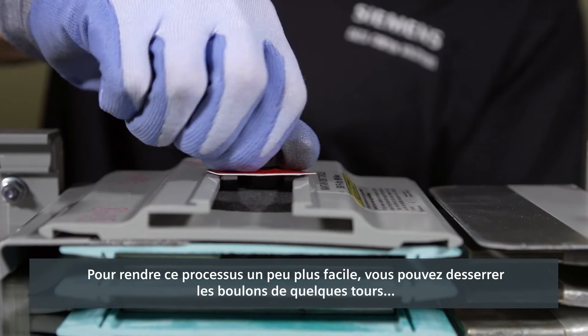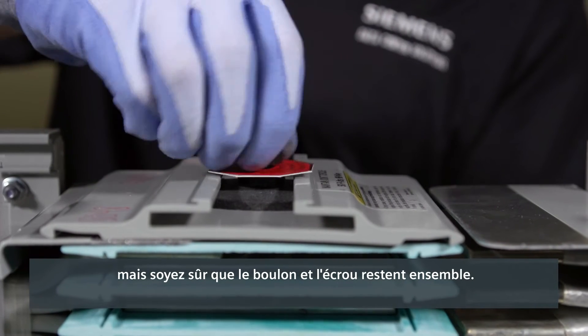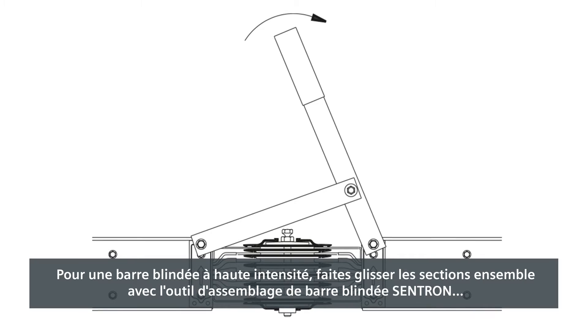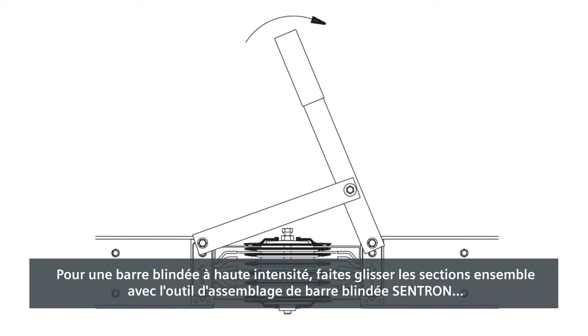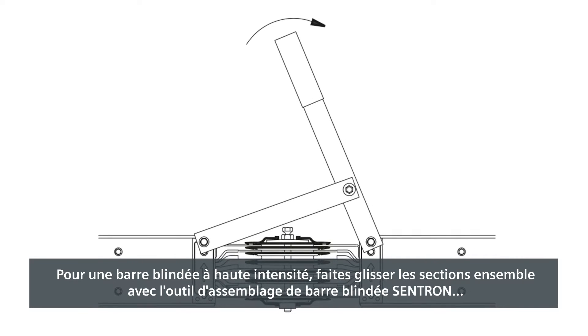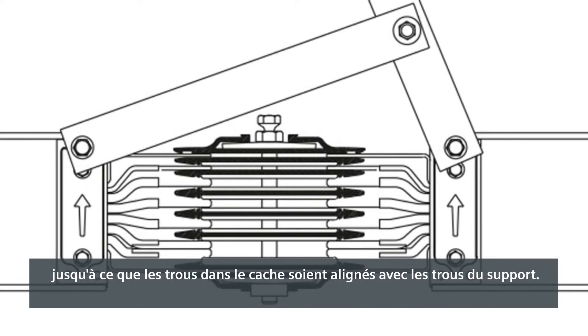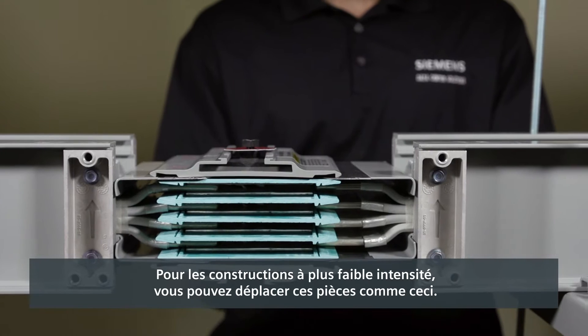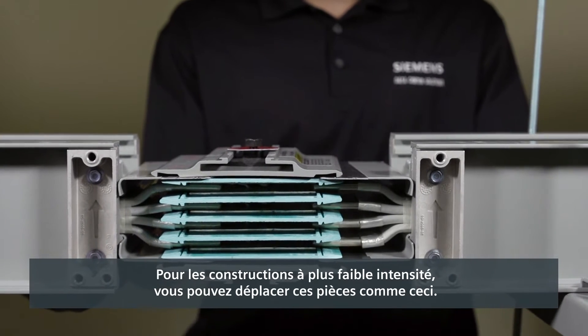To make this process a little easier, you can loosen the joint bolts a few turns, but be sure the joint bolt and the joint nut stay together. For high amperage busway, slide the sections together with the SENTRON busway assembly tool until the holes in the joint cover align with the holes in the joint support. For lighter amperage constructions, you can move these pieces together by hand.